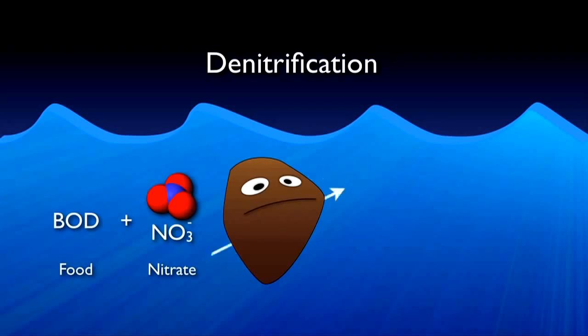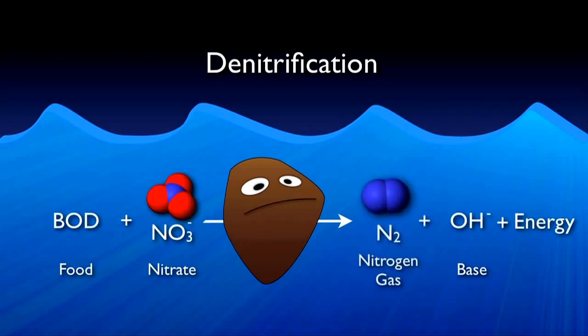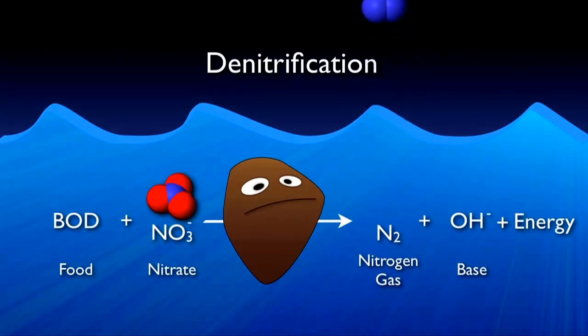These bacteria take the BOD and nitrate to produce energy, base, and nitrogen gas. The base is useful in buffering the acid produced during nitrification. The nitrogen gas then floats in tiny bubbles to the surface and into the atmosphere. Though denitrification is great in the biological basin, denitrification occurring in a clarifier can result in undesirable floating sludge.